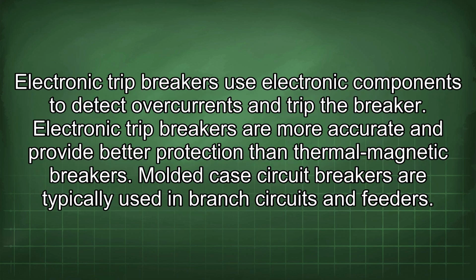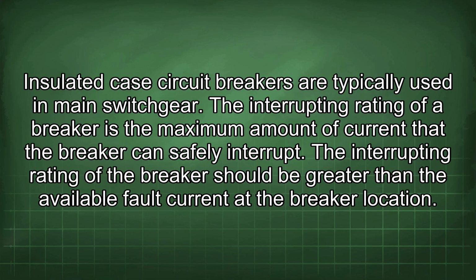Electronic trip breakers use electronic components to detect overcurrents and trip the breaker. Electronic trip breakers are more accurate and provide better protection than thermal magnetic breakers. Molded case circuit breakers are typically used in branch circuits and feeders. Insulated case circuit breakers are typically used in main switchgear.